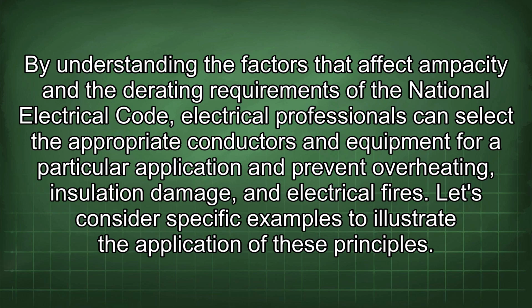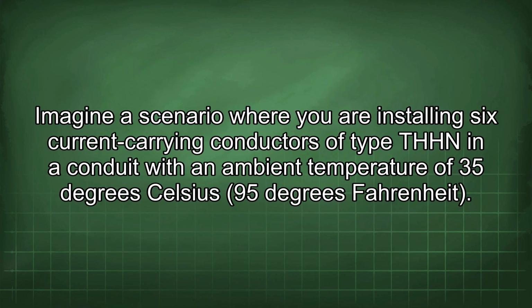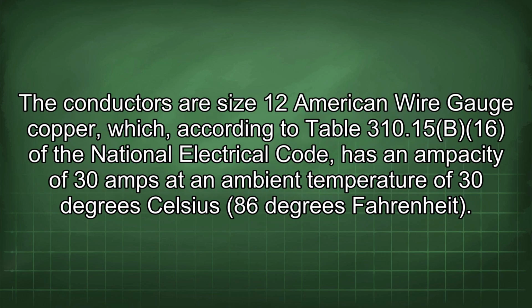Let's consider specific examples to illustrate the application of these principles. Imagine a scenario where you are installing 6 current-carrying conductors of type THHN in a conduit with an ambient temperature of 35 degrees Celsius (95 degrees Fahrenheit). The conductors are size 12 American wire gauge copper, which, according to Table 310.15(B)(16) of the National Electrical Code, has an ampacity of 30 amps at an ambient temperature of 30 degrees Celsius (86 degrees Fahrenheit).